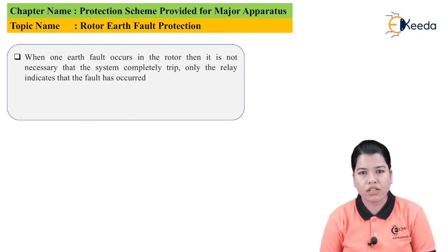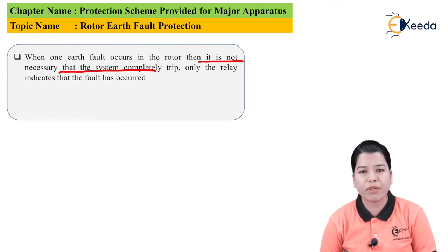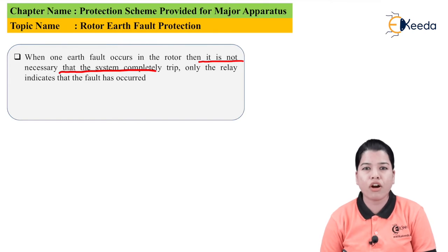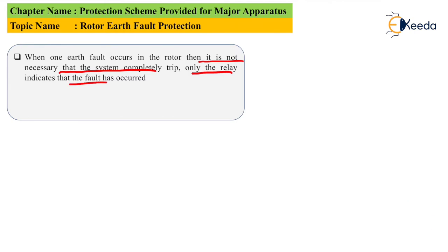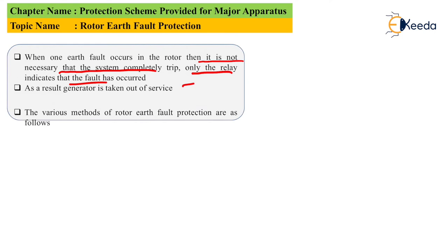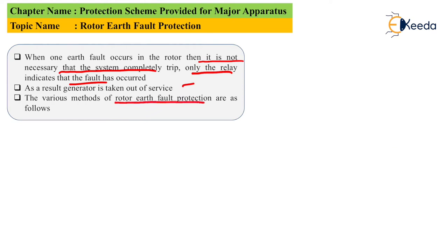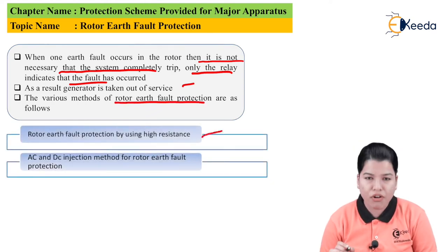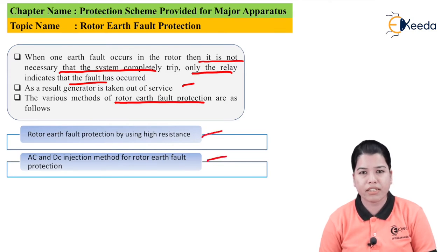When one earth fault occurs in the rotor, it is not necessary that the system will completely trip, because there is no rise in fault current and the system will not consider it as a fault condition. The system will not trip — only the relay will indicate that the fault has occurred. As a result, the generator can be taken out of service. The two methods of rotor earth fault protection are: first, rotor earth fault protection using high resistance, and second, the AC and DC injection method.